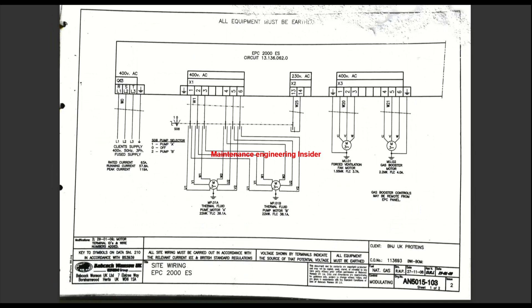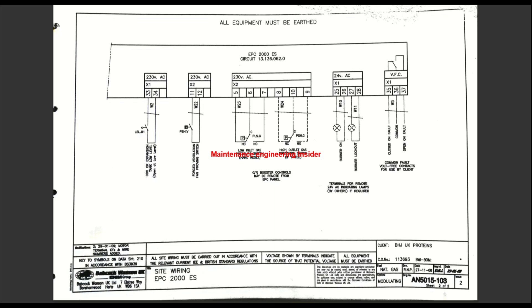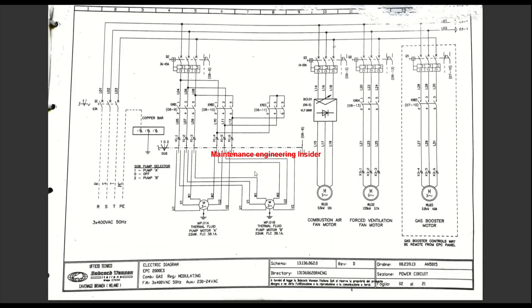These thermal fluid pumps are not running. There are two thermal fluid pumps — pump A and pump B — each with similar characteristics: 22 kilowatts and 38.1 amps. These two pumps are not meant to run together; they are switched by a selector switch in position one, zero, or two. In zero it's off; in one it runs pump A; in two it runs pump B. We're not able to get either of them to run, so we want to know why.